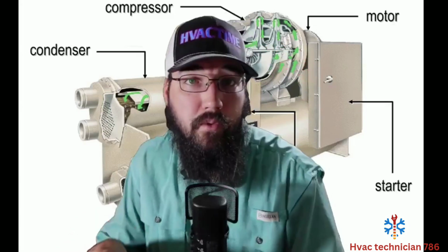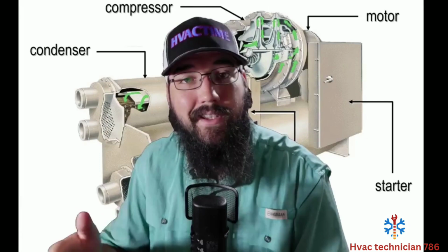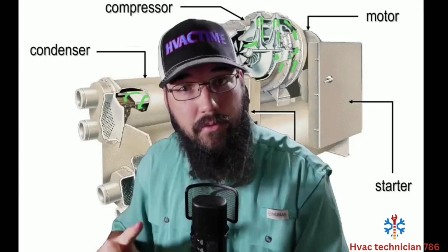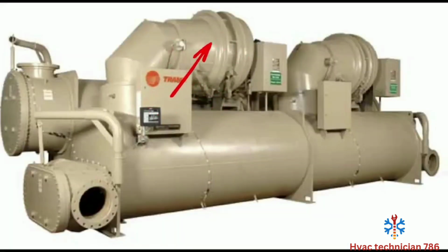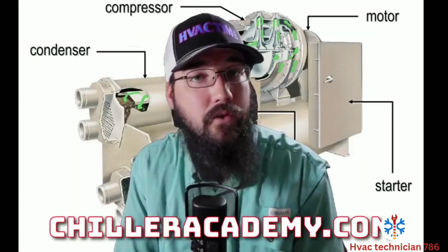One of the requests I got was a refrigeration cycle for a CDH. This is it. The main difference being is there's two of these systems sandwiched together. Let me show you. So with a CDH, it's quite literally just, here's one CVHF, here's a second CVHF. These could be CVHGs as well, which would be a 3-stage, and they're just smacked together end to end. The heat exchangers are just welded together on the same end plate. Water flows through, everything happens just the same. And these are two independent circuits. They operate independent of one another. They do not cross their oil circuits, refrigerant circuits, or anything else. They are fully separate from one another. And that is your primary refrigerant cycle for a Trane centrifugal chiller.